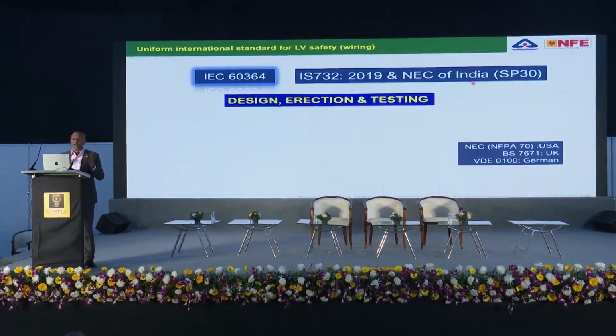The same document also exists in India, which is called NEC, the National Electrical Code of India. The latest one was published in January 2023. This particular document explains the design, erection and testing of an electrical installation. In fact, testing is not the correct word, verification is the word. NEC is not a product standard. It does not say anything about a product like wire, what quality of wire, what quality of switch, what quality of MCB. That is the problem of the product manufacturer. That is the product standard, whereas NEC is an installation standard.